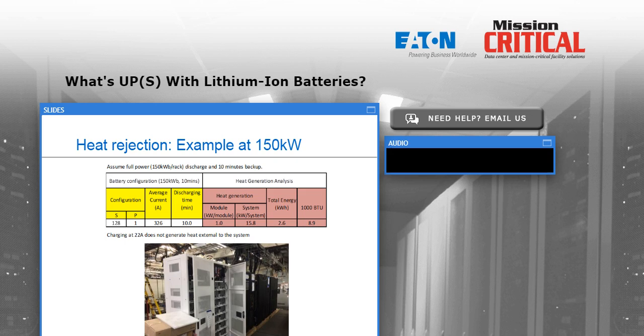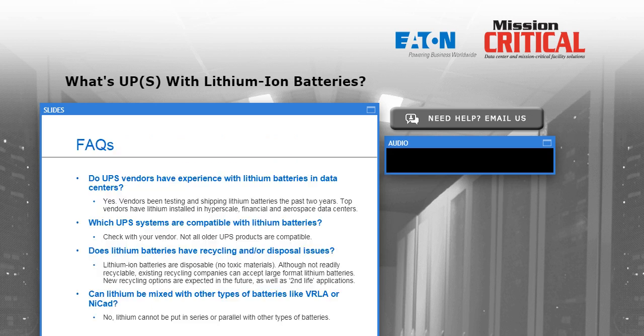So typically not enough to impact the air conditioning of the room, as long as the air conditioning in the UPS and battery room remains functional during the discharge and doesn't shut off due to the generator not starting or the air conditioning not connected to a generator, those kind of things. But generally, there's no concern about heat rejection with a lithium battery above and beyond what we would normally do for a valve-regulated lead-acid battery. Now, the next two slides are some frequently asked questions, and as soon as we do these, we're going to throw it open for questions that you guys can pose.